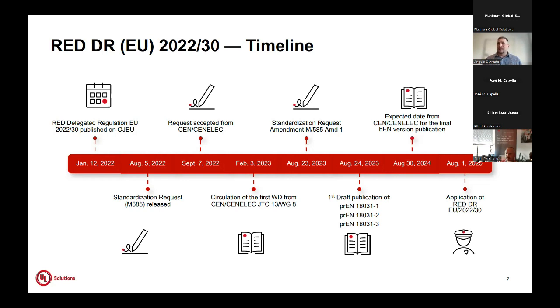But of course, that doesn't mean this harmonized standard will be thrown away. Manufacturers can still use it, but the only problem is that if the standard is not published in the official journal, they are forced to go through a notified body for the EU type certification, so module B and C.